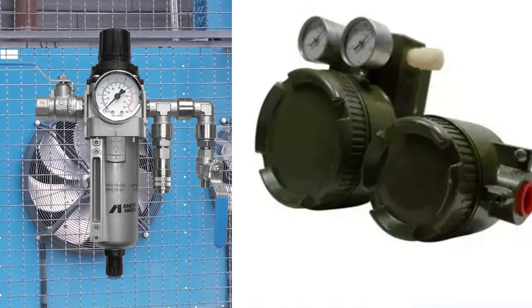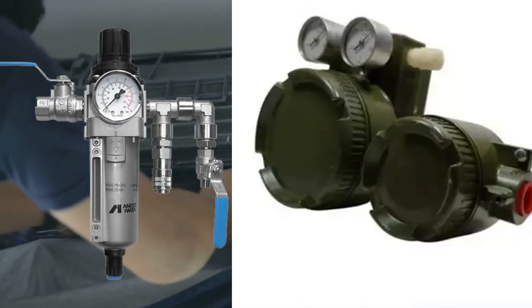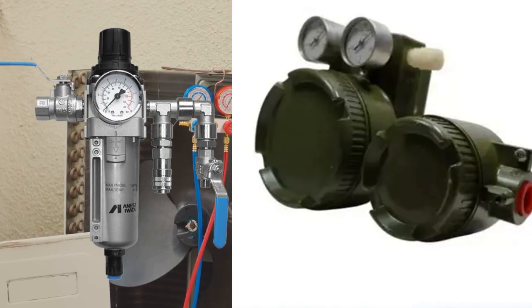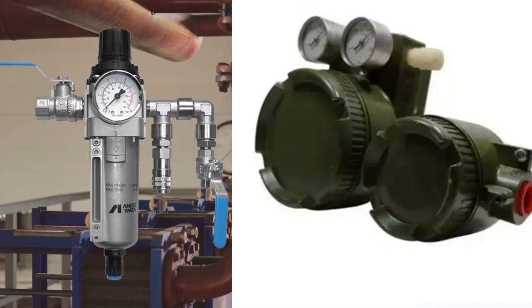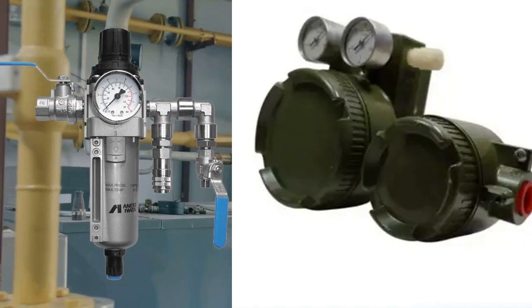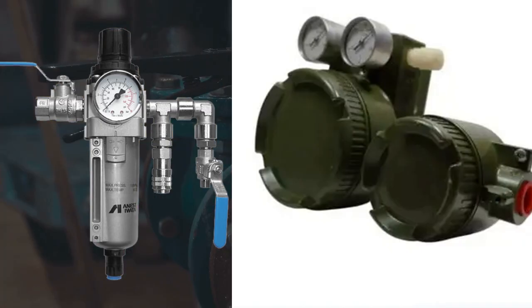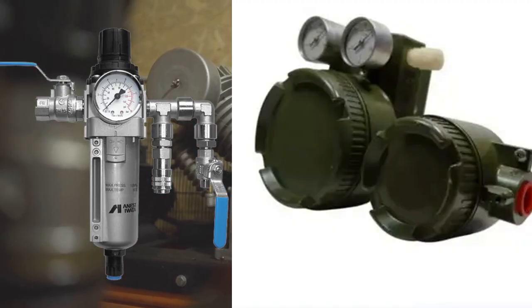First up, air supply. Dirty, oily, or wet air is a killer. If your compressed air isn't clean, the internals of your IP converter can get clogged, nozzles get gummed up, and suddenly your valve isn't moving. Or worse, it's moving unpredictably. And don't even get me started on supply pressure. Too high, too low, or just plain unstable. That's a recipe for output that's all over the place.